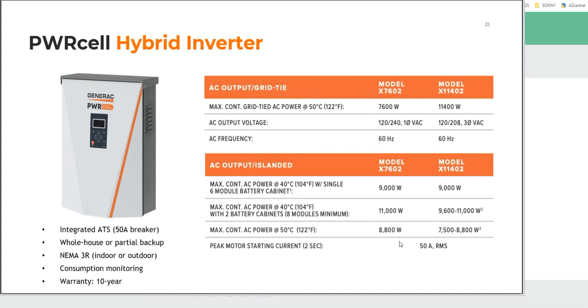Most importantly, I think we should take a look at these values, particularly in how they compare to other manufacturers. This one is really important. When you're talking to customers about battery storage and backup power, this is a very important value. Being able to drop 50 amps onto a load for a couple of seconds is the difference between getting water out of the ground and not, in many cases.